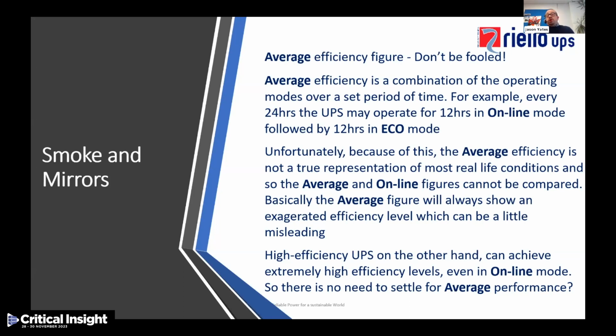For example, a UPS system could be operating over 24 hours, and for 12 hours of that it could be in online mode, and for the remaining 12 hours it could be in eco mode. Because of this, the average efficiency is not really a true representation of real-life conditions, and so the average and online figures can't really be compared, unless you're operating it that way. The average figure will always show an exaggerated efficiency level, which can be somewhat misleading. High efficiency UPSs, on the other hand, can achieve extremely high efficiency levels, even in online mode. So there is no need to settle for average performance.